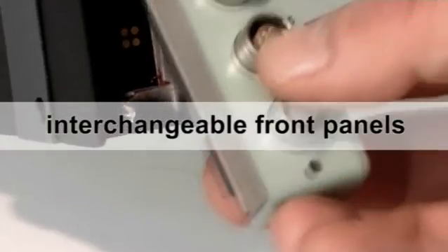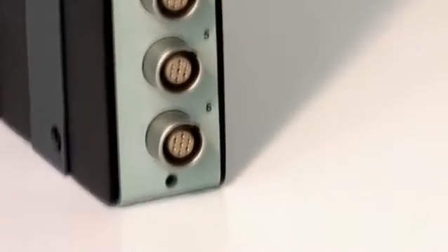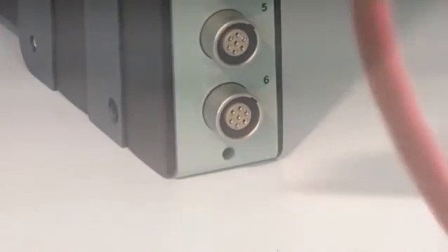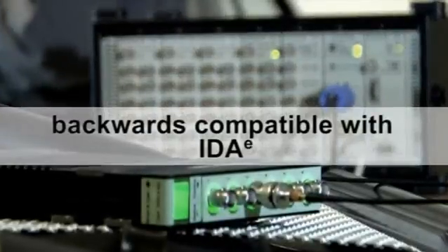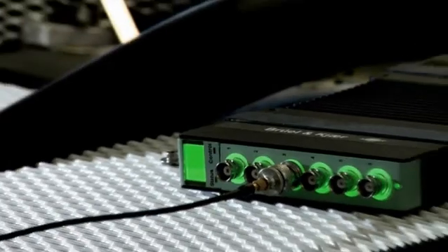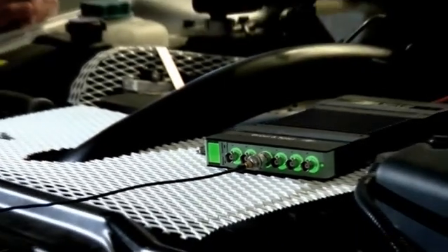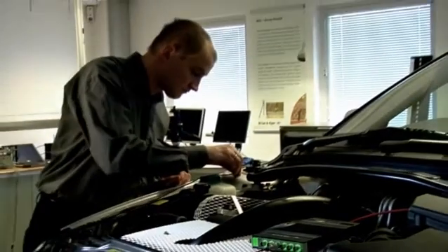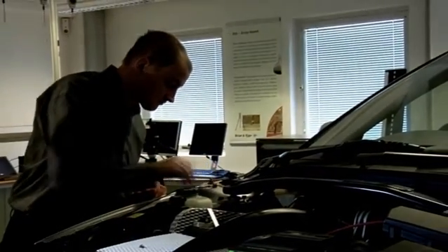Interchangeable front panels let you decide which cable type to use and make for an easy swap of transducers, so less hardware is needed. And the option for mains, battery or LAN powering again means fewer cables. LAN-XI is backwards compatible with your existing IDAe hardware, allowing you to combine the two and still maintain sample and phase accurate measurements, so you get the latest technology without having to make a major new investment and without having to discard your old hardware.